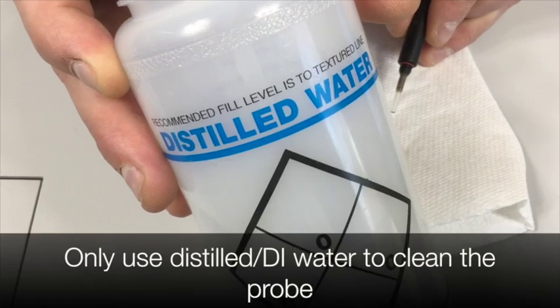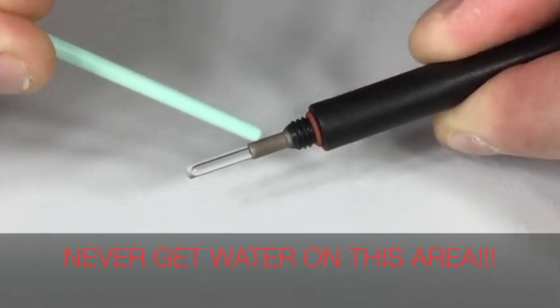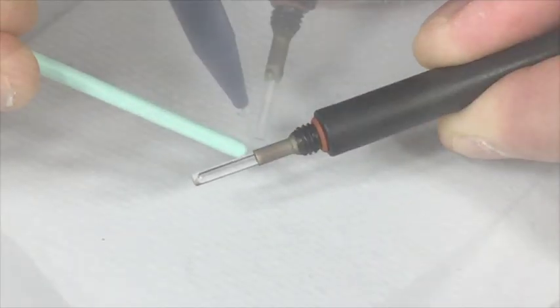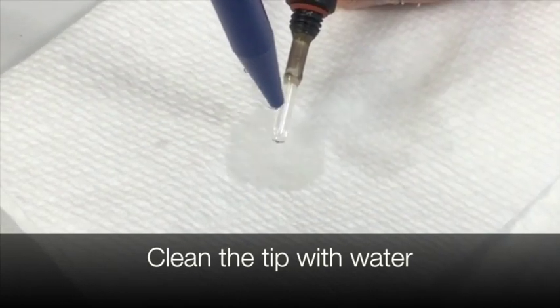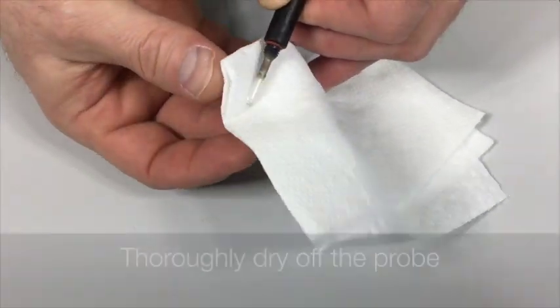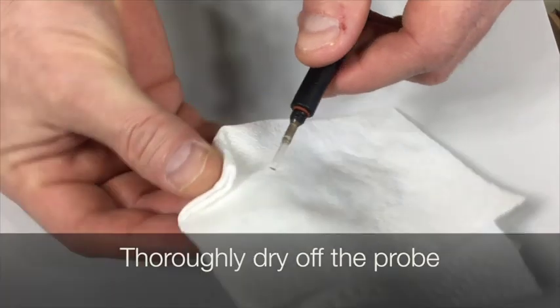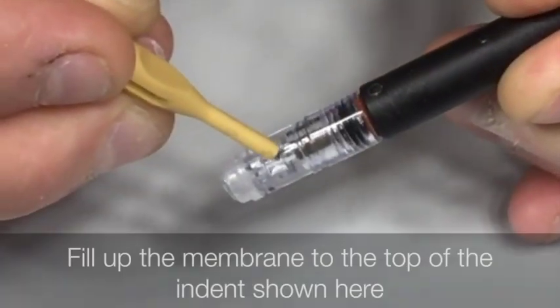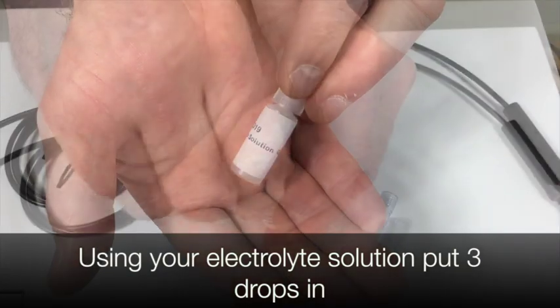Only use distilled or DI water to clean the probe. Never get water in this area. Clean the tip with water. Thoroughly dry off the probe. Fill up the membrane to the top of the indent shown here. Using your electrolyte solution, put 3 drops in.